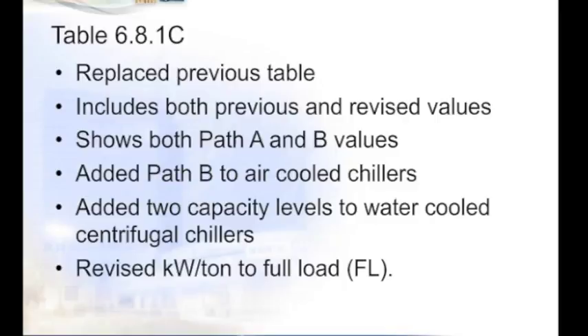And you'll note when you look at the table that almost everything is underlined, indicating all the additional and replaced information. Even the footnotes are changed, which I think the only exception is note C. That was the only one that I think hadn't changed. The table is represented in the addendum in both inch-pound as well as in SI units. It shows both Path A and Path B values where they apply. It added Path B to air-cooled chillers, which wasn't there before. It also added two capacity levels, 300 to 400 tons and 400 to 600 tons, to the water-cooled centrifugal chiller category. It also revised some nomenclature by adding full load, or FL, in lieu of just units, kW per ton, which it had before.